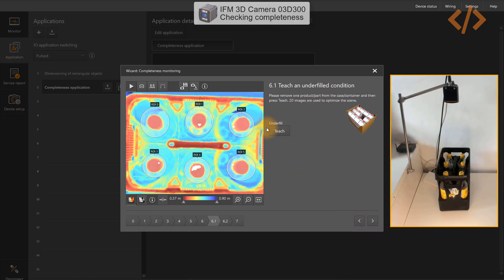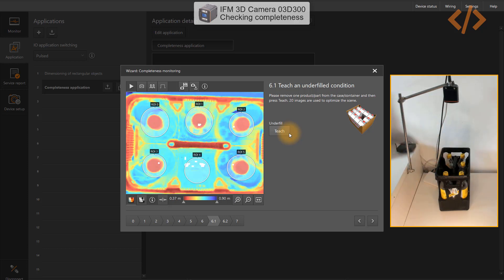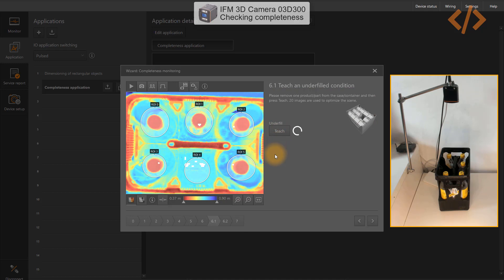Now it will ask you to teach the underfill state. I have to remove one bottle so the camera learns what the region of interest signal looks like when it is underfilled. I took the bottle out from region of interest 4 — segment 4 — and I click Teach. It finds the difference in the image when the bottle is present versus absent. Once you have the tick sign, go to next.